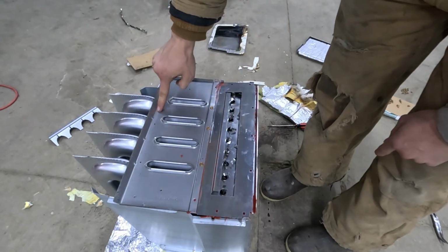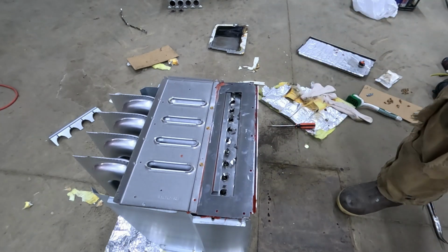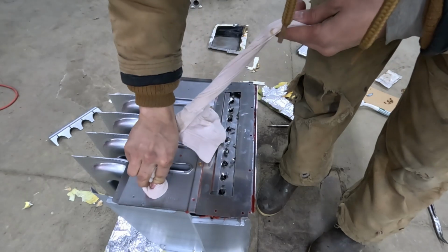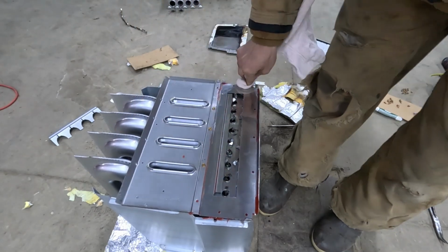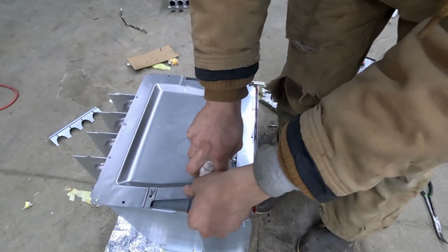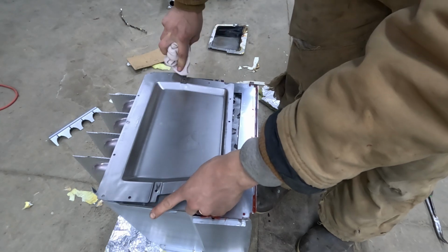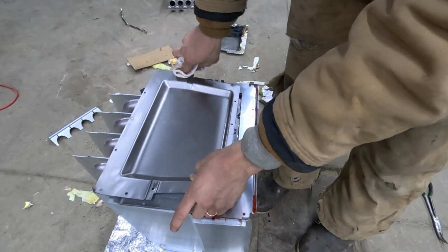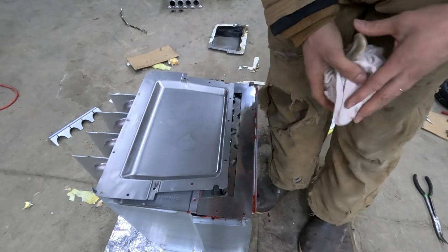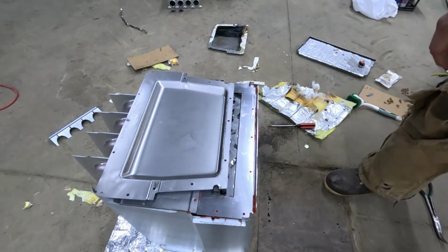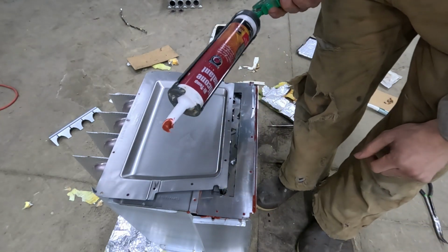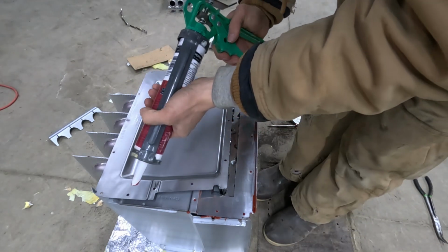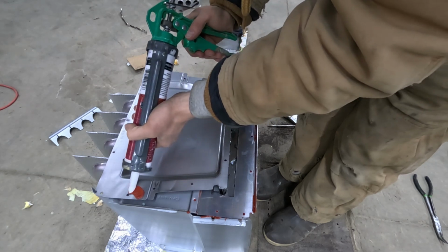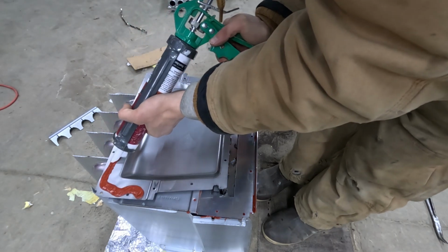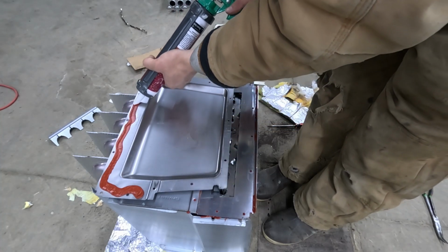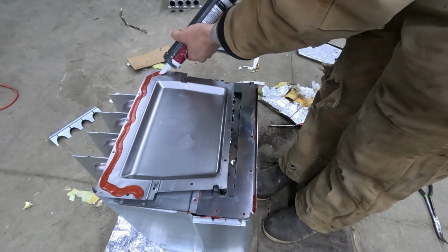Now our next piece is going to go on right here, so we'll carefully wipe down that exposed silicone path. Usually if these things have a heat exchanger replaced once, they're not going to have another one replaced, because the first one is under warranty, and after that you have to buy it yourself, and it makes more sense to buy a new furnace. A lot of people comment on the other video asking why we'd put a new heat exchanger in. The answer is the only time we pretty much recommend putting in a new heat exchanger is if the unit has it under warranty. Otherwise we usually don't recommend it.